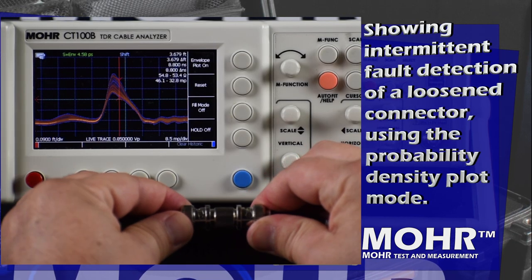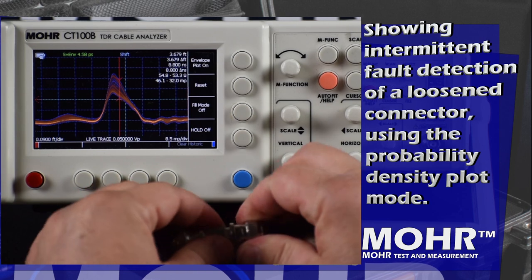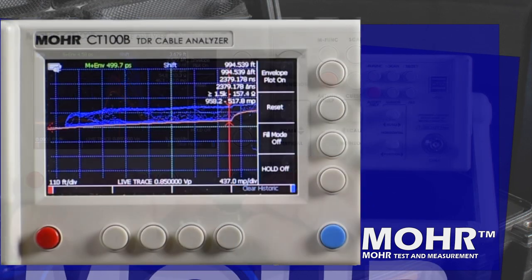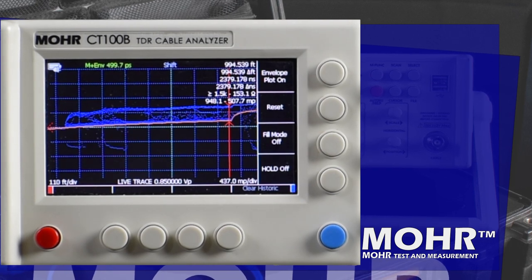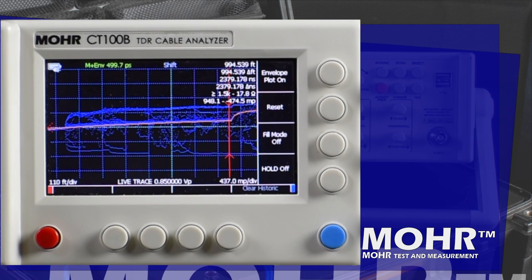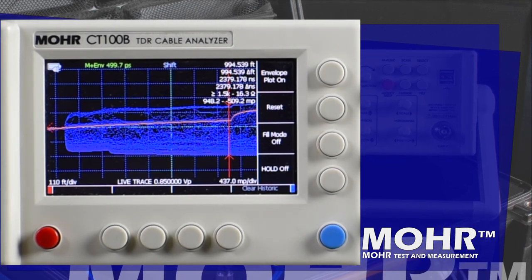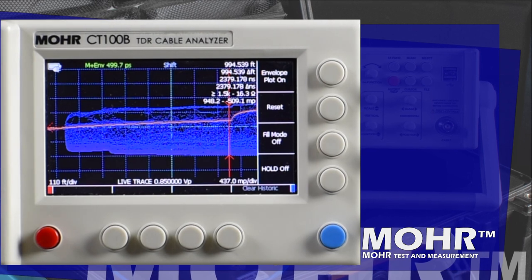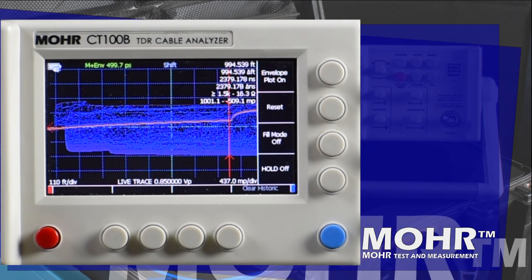Envelope plot makes it easier for technicians to find and locate intermittent faults down to connector level detail, even multiple faults, as seen here in this 1,000-foot cable. A single technician can connect to the device under test, do a full visual inspection while manipulating known potential problem areas, then see the results recorded on the screen.